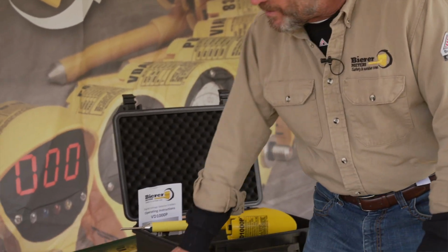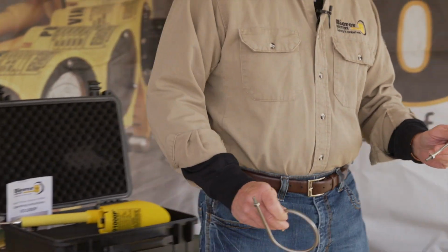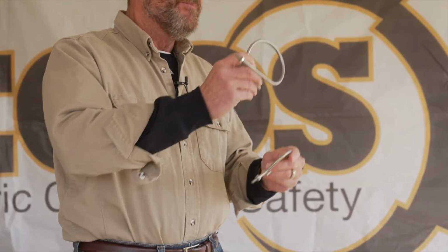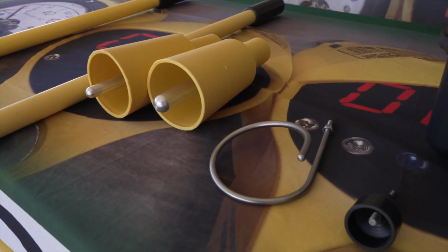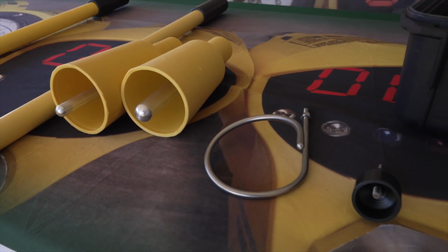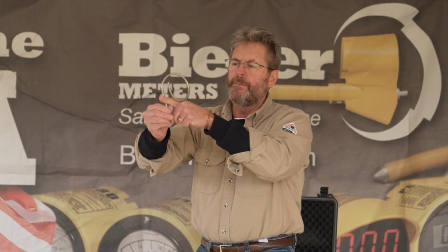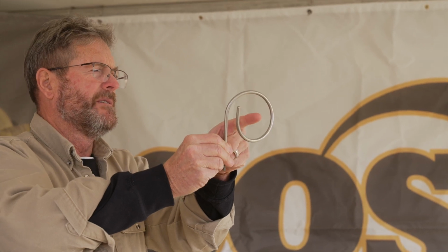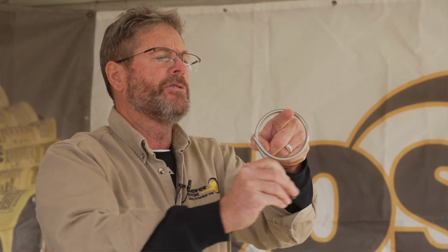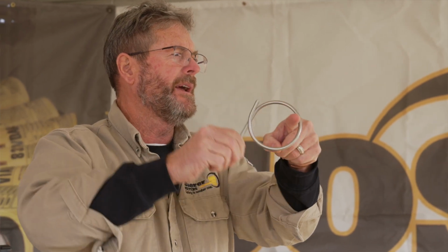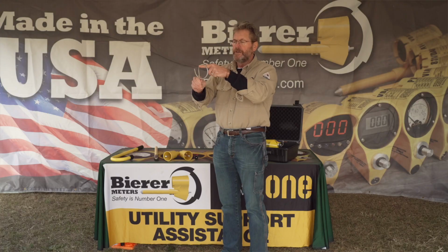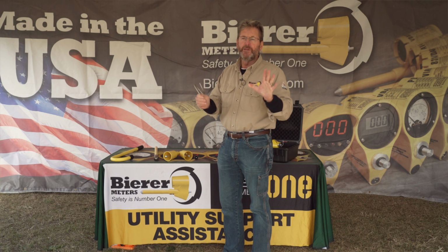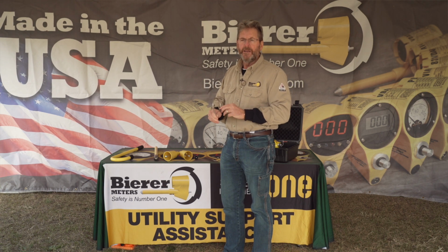You can add the pigtail to your meter. The pigtail is used on your meter in cases where you have a high wind scenario, so the tool can be left on the line. You just simply come into your line at an angle and then twist. Very simple. It'll allow your tool to rock back and forth on that line without blowing off the line. Very nice accessory to have if you live and work in high wind locations.